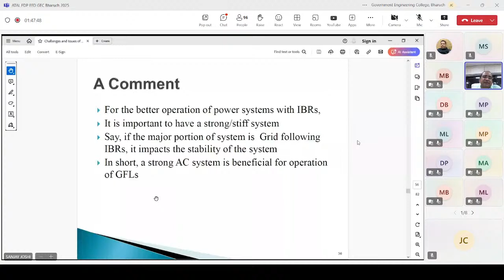Okay, so for better operation of a power system with IBRs, it is important to have a strong and stiff system. Already I have made a point here in one slide. If a major portion of the system is grid following IBRs, it is not grid forming, grid following, it impacts the stability of the system. In short, a strong AC system is beneficial for operation of grid following inverters, right? If the penetration of grid following inverters is very huge, then it is not a good situation, right?